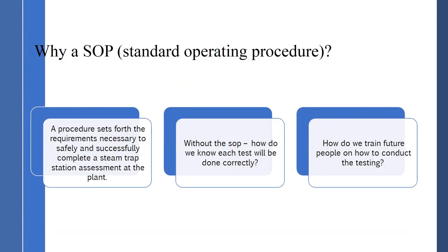A procedure sets forth the requirements necessary to safely and successfully complete a steam trap station assessment at the plant. The procedure ensures that people can go out, conduct a steam trap testing assessment, and have it be repeatable and accurate every time. Without an SOP, how do we know each test will be done correctly? We can't just assume the person knows what they're doing. Without that, we will not get repeatability — that's the reason for an SOP.